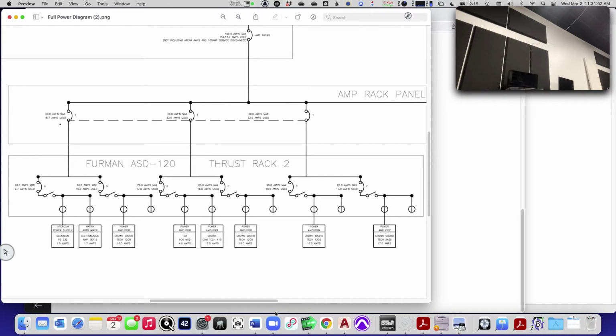You don't have to diagram this, but the sequencer will do A, B, C, and then D, E, F. Theoretically, you could have 20 and 20 here, and that would match the 40 on that breaker, and that's fine. But what you don't want is for both of these to switch on at the same time with inrush current, and we could potentially exceed it. That probably wouldn't happen if this really is 40 amps and these really are 20, but just in case.